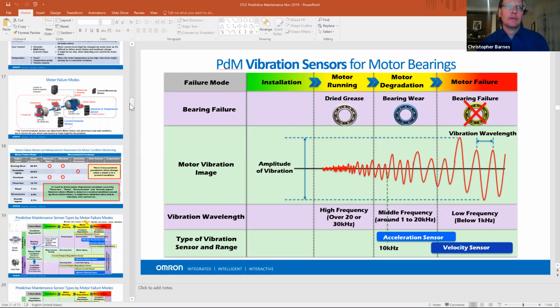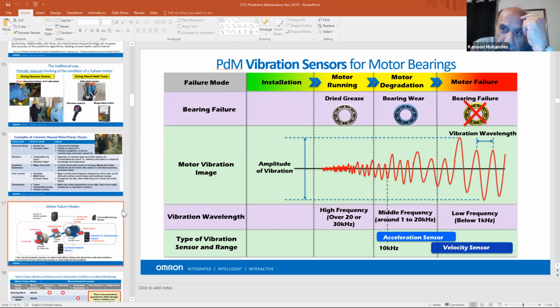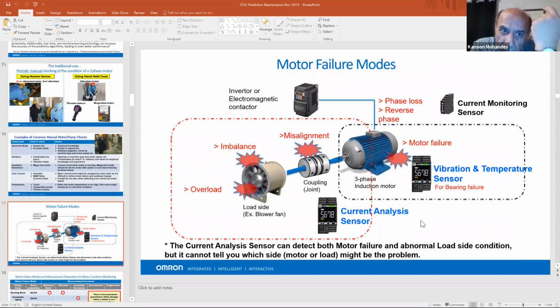Does that help answer your question? It doesn't impact the situation of the motor itself, but running it faster or slower would impact the current sensors, because when you're changing the variable frequency or variable speed drive, you're changing the amount of power you're putting in to make it turn faster or slower. So some of that will show up in the current analysis, but in the vibration analysis, you'll see some depending on the load.